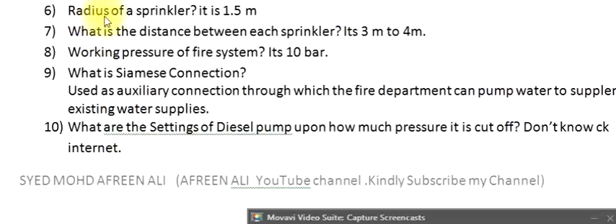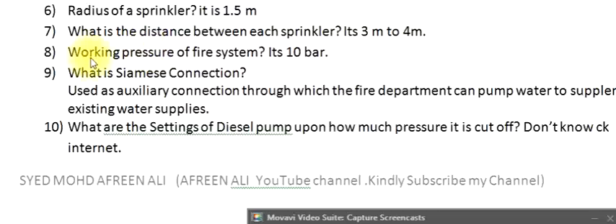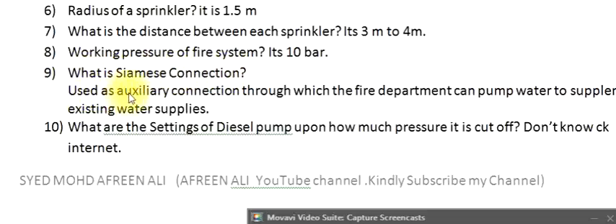Question 6: Radius of a sprinkler? It is 1.5 M. Question 7: What is the distance between each sprinkler? It's 3 M to 4 M. Question 8: Working pressure of fire system? It's 10 bar. Question 9: What is Siamese connection? It is used as an auxiliary connection through which the fire department can pump water to supplement existing water supplies.